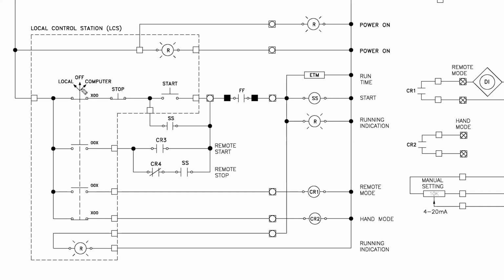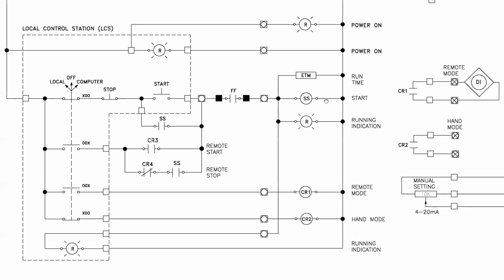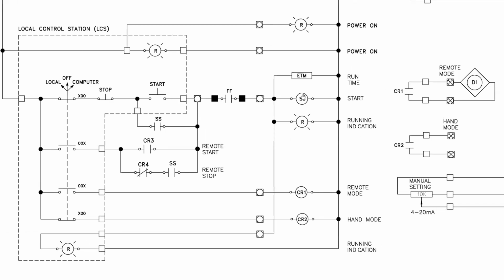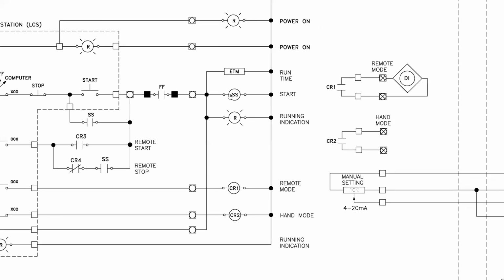So when you see these type of linked, again, this is linked just like that other switch we saw in the lighting panel. This is physically linked. So this is all the same button. And when this switch changes, when it's in local, these push buttons start, stop, FF. I'm not sure what that is, a fault of some sort. This is the starting circuit for the pump. So you can start it. It'll close in SS, which is the start here. When SS closes, it looks like that's the indication that this drive is going to run the pump.